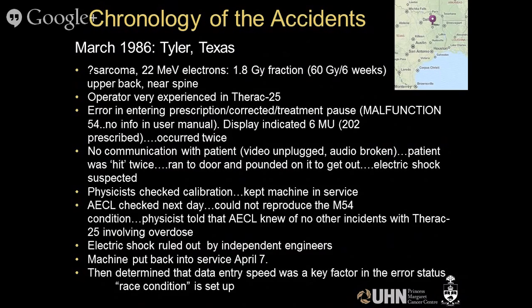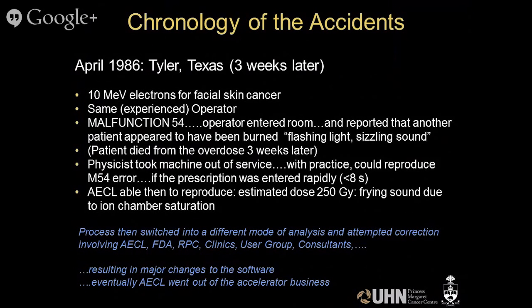The machine was put back into service, and subsequently it was determined that the data entry speed was a key factor. This operator being very experienced meant that when setting up the conditions, she was able to type very fast, and it turns out that that's actually likely an unacceptable safety condition.